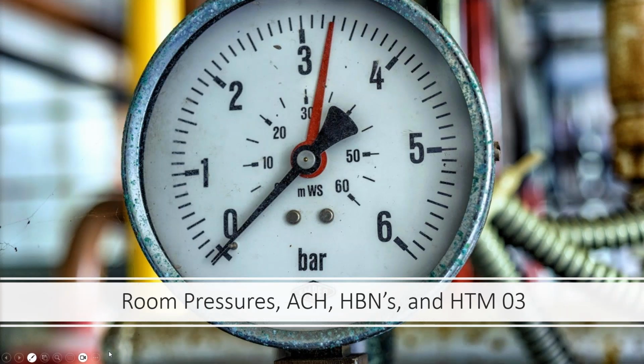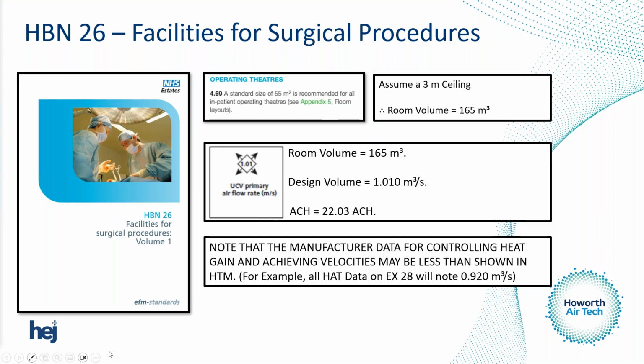So room pressures, air change rates, HBNs, HTMs, how do we tie them all together? Without doing a full presentation on health building notes and architectural design of clinical spaces, I thought I'd take something relatively straightforward and easy to explain. If we look at HBN 26, paragraph 4.69, it says the standard size of an operating theatre is 55 metres squared. It doesn't give us a height, so it doesn't give us a volume, but let's assume a 3 metre ceiling within the operating theatre.